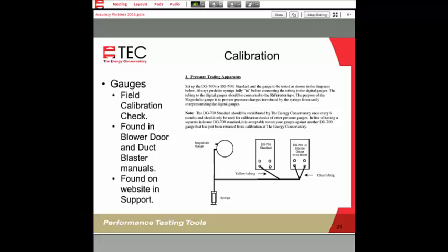And we see this done fairly often. Any organization that has a number of gauges, depending on your provider and who's overseeing your work, will accept the fact that you've done this sort of calibration check. You've logged all the data, you've kept it. This is how many times I've tested this gauge. And then over time, they might take the second gauge and send that back to TEC, and then compare the other gauges the next year. So it's just a process where you're able to do that.